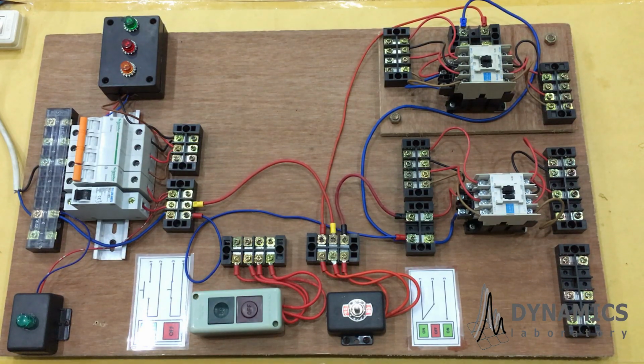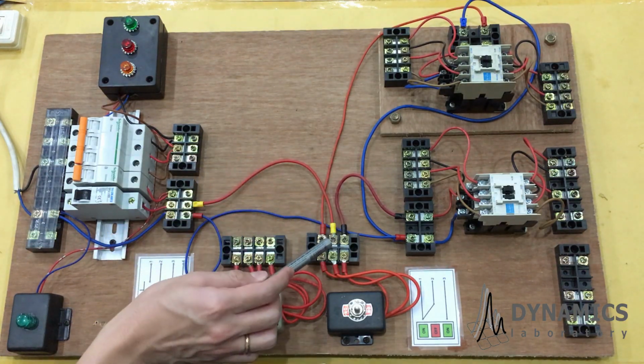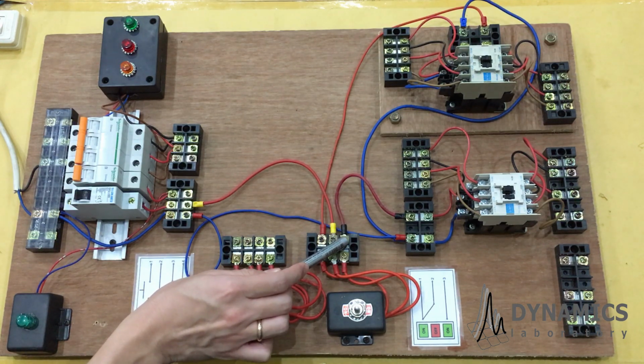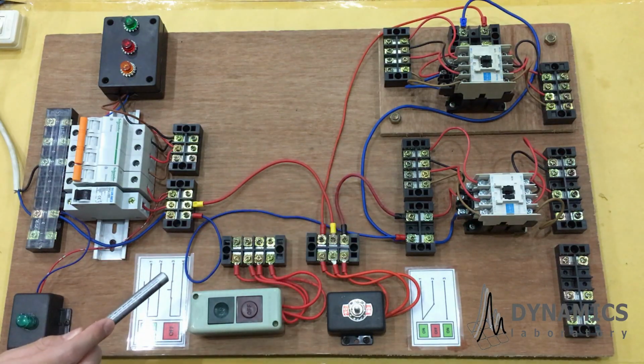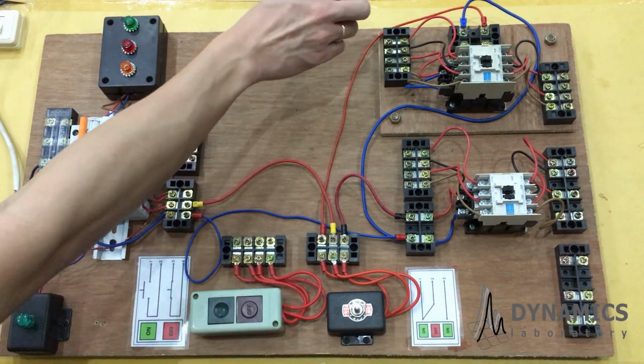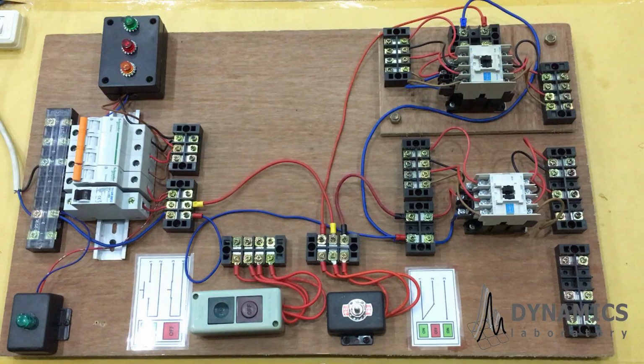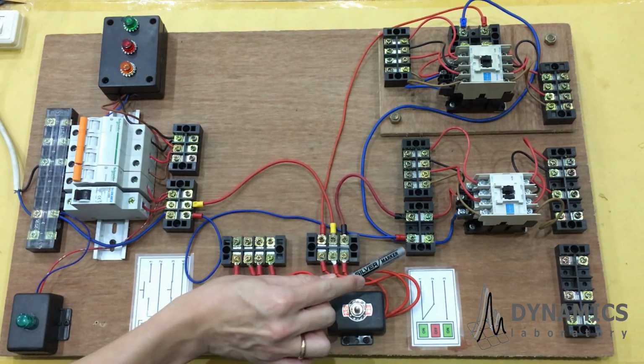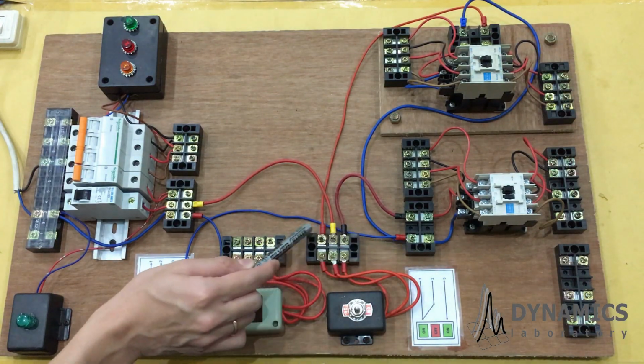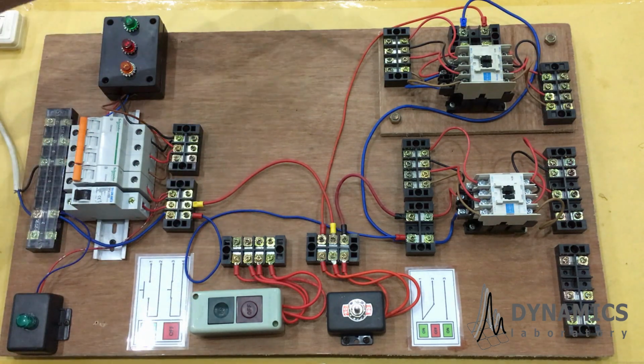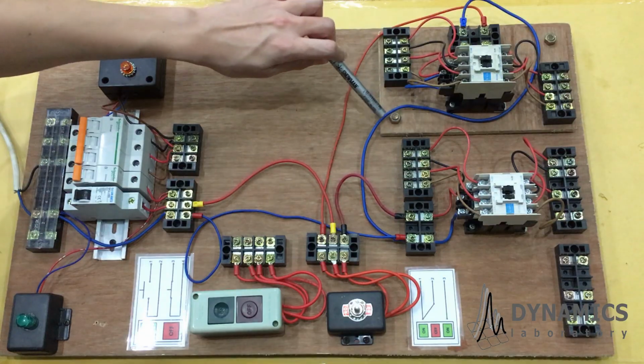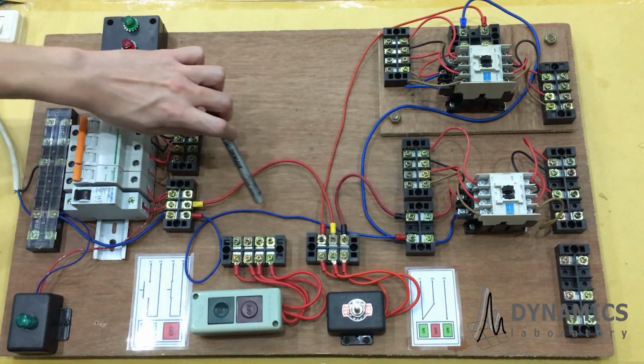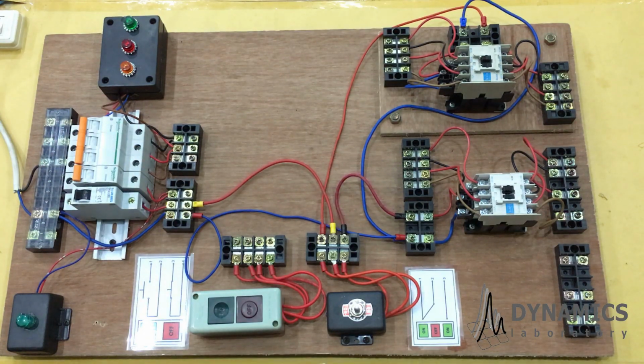Switch control circuit. Normally, a switch control circuit is used when you want to control two contactors. Look at here. From the control circuit breaker to the middle leg of the switch. The right leg of the switch is connected to coil contactor 1. Meanwhile, the left leg of the switch is connected to coil contactor number 2 in here. To complete the circuit, you also have to connect the coil contactors with the neutral terminal. As you can see in here, the blue cable of the coil contactor is connected to the neutral terminal. And the same in here. The blue cable of the coil contactor is connected to the blue cable of the contactor in here, and finally it reaches the neutral terminal. Let's try.